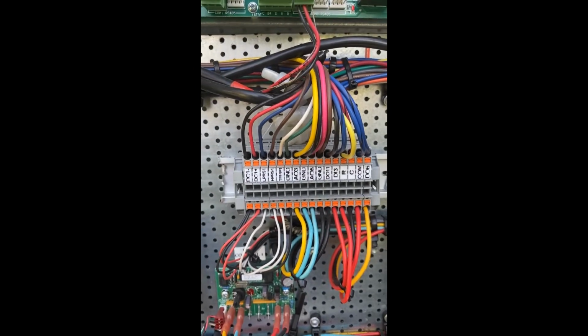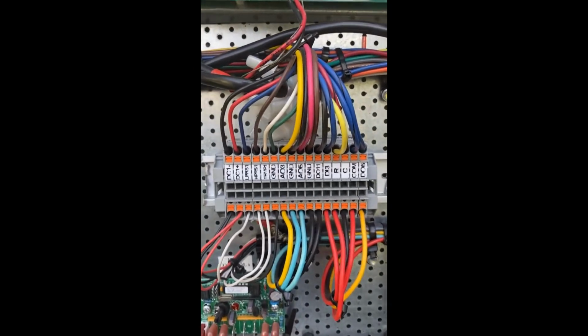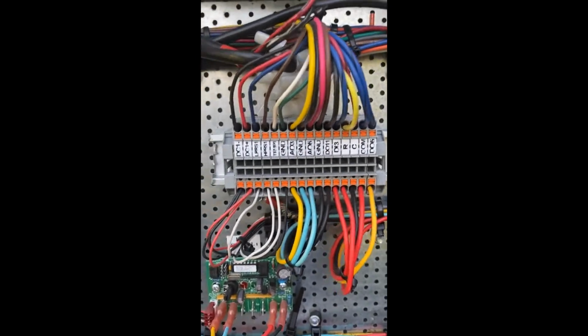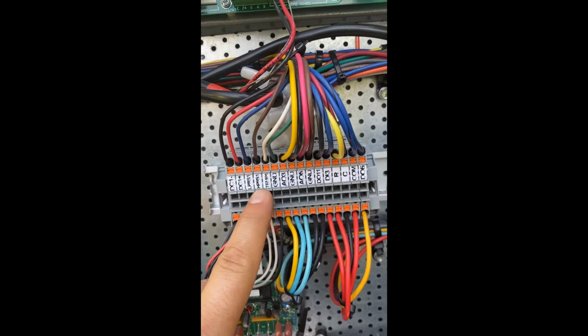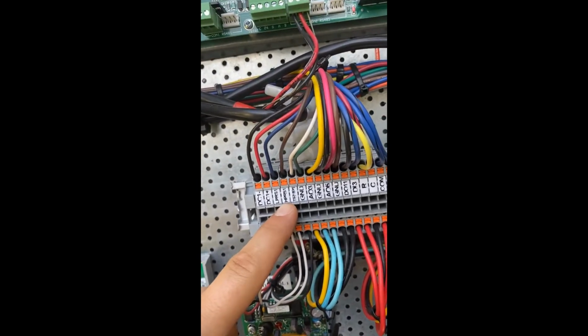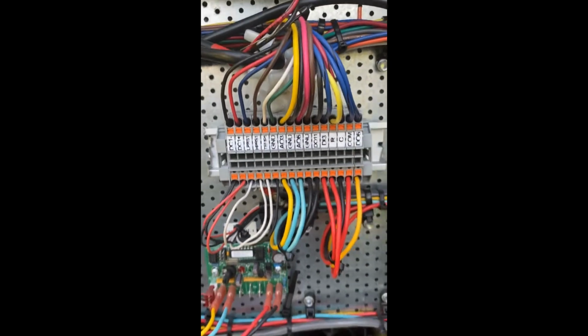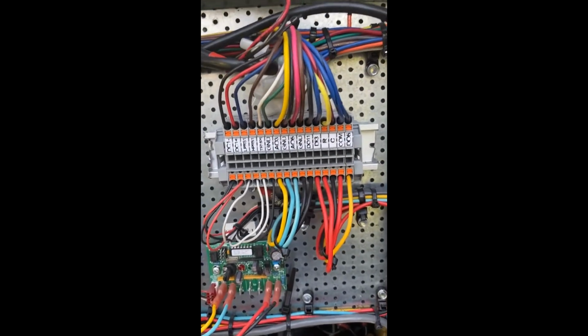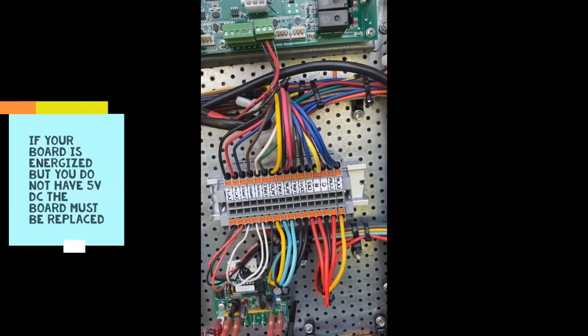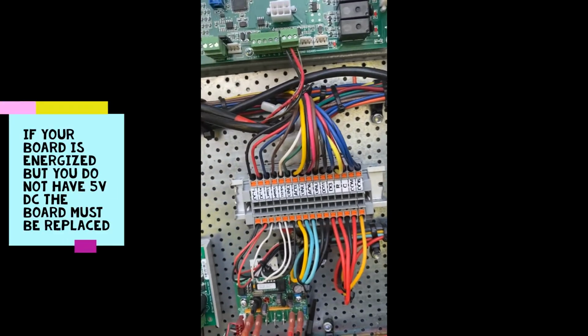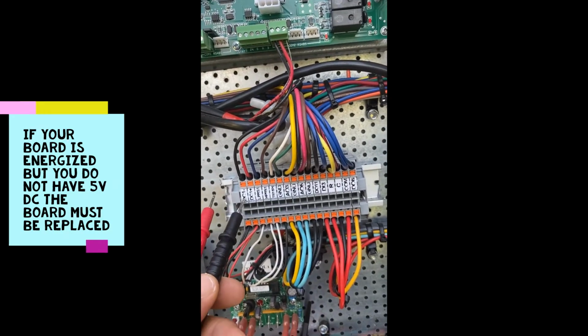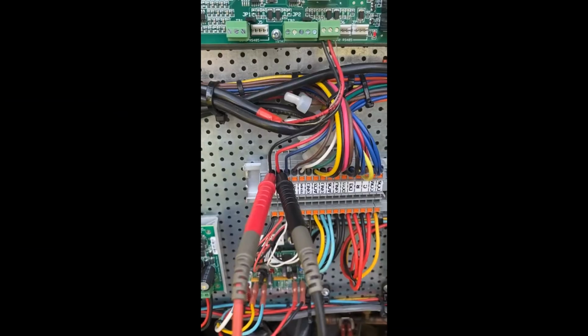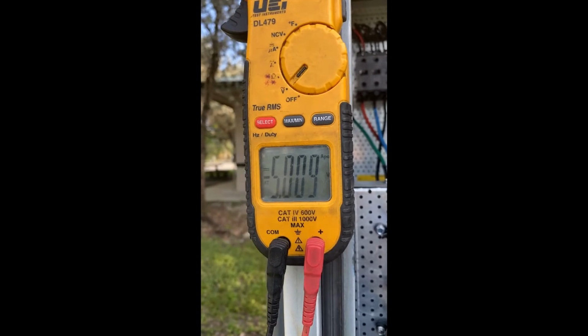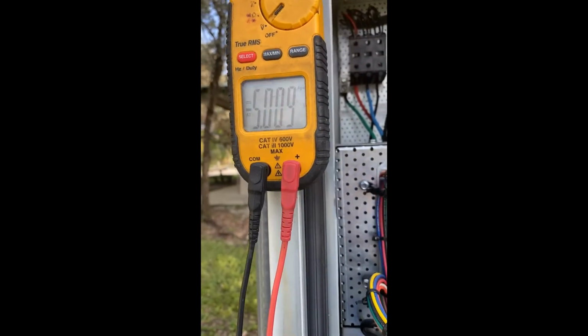So here's where your DC block is for your sensors, like your suction transducer is low pressure here, and then high pressure is your high pressure transducer. So just a quick way to know that your board is actually sending out the right signal. It should send about 5 DC volts. So we're going to check that right now. Between these two terminals at the beginning here, you'll see DC negative, DC positive. All right, so I got my leads in there, and you could see I have 5 volts DC. You got to check on DC. All right, so we know our board is good.